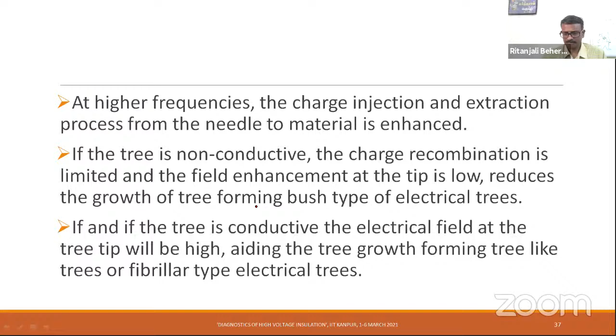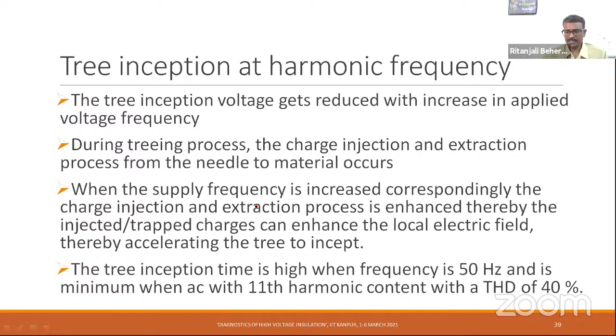Tree inception. In fact, I should have spoken this a little earlier. The tree inception voltage gets reduced with the increase in the applied voltage frequency. During the treeing process, the charge injection and extraction process from the needle to material occurs. When the supply frequency is increased, correspondingly, the charge injection and extraction process get enhanced. And so the injected and the trapped charges will enhance the local electric field at the tip, which causes the tree branch to incept. So the tree initiation time is high when the frequency is 50 hertz power frequency, and becomes very less and minimum when it is present with 11th harmonic content with the THD of about 40%.